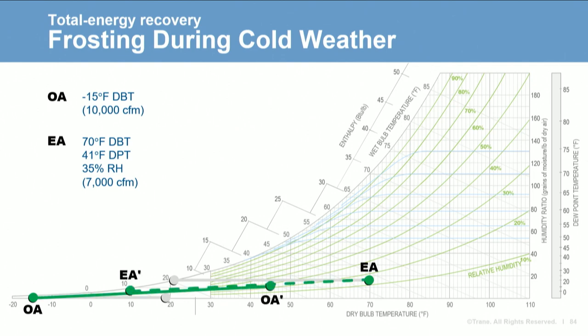Since sensible recovery devices do not transfer water vapor, the leaving exhaust air condition reaches saturation and freezes at warmer outdoor temperatures than it would for a total energy recovery device. However, with any technology, depending on conditions, some method may be needed to prevent frosting. It involves either reducing the heat recovery capacity of the device or preheating the air before it enters the device. Coil loops typically use a three-way valve to keep the fluid temperature warm enough so the exhaust side coil surface doesn't drop below the current frost point or 32°F. Heat pipes and wheels can modulate bypass dampers or supply side bypass dampers to reduce heat transfer and prevent frosting.